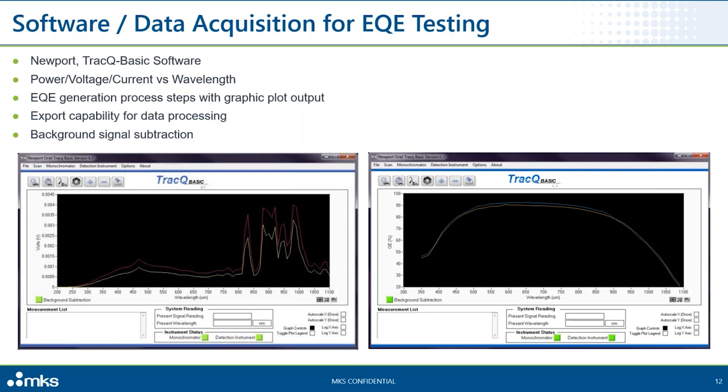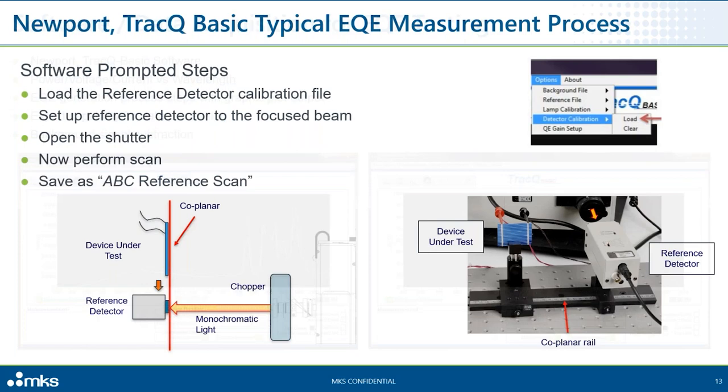And then also, the software allows you to do an EQE. And it also has the ability, especially if you're using a DC type of testing, to subtract background signals or background noise. And we can go to the next slide.